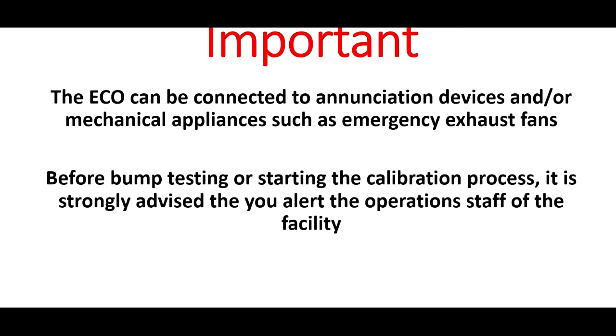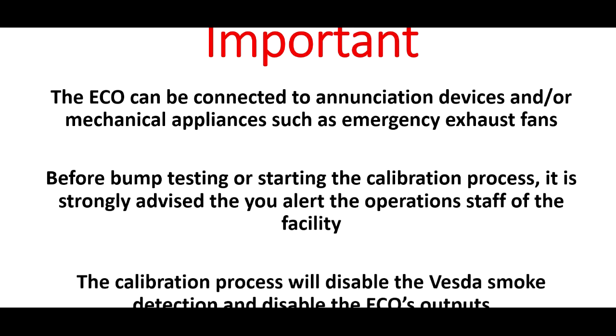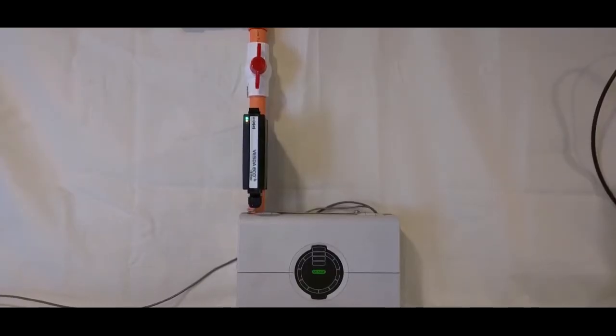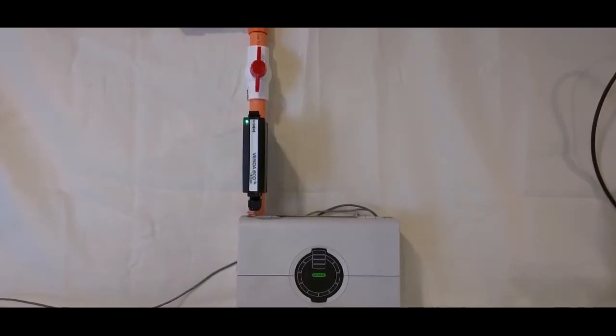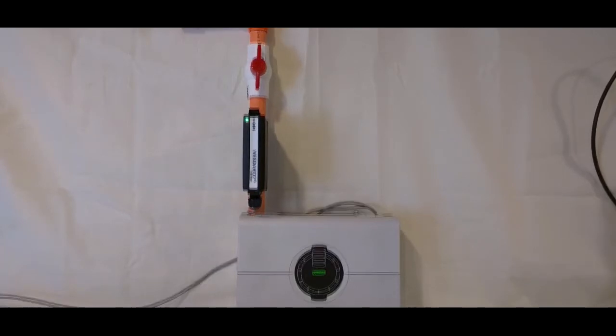Before bump testing or calibrating an ECO, alert the operations staff of the facility. When bump testing the ECO, its outputs will be live and will place the detector into alarm. It is important that no airflow is going through the ECO detector before calibration. Airflow through the ECO will dilute the test gas and prevent an accurate reading.